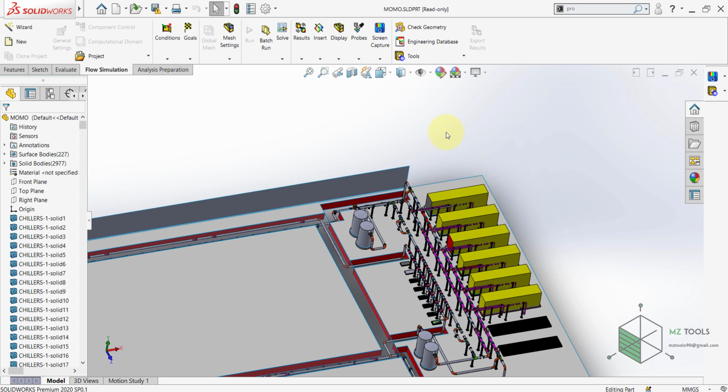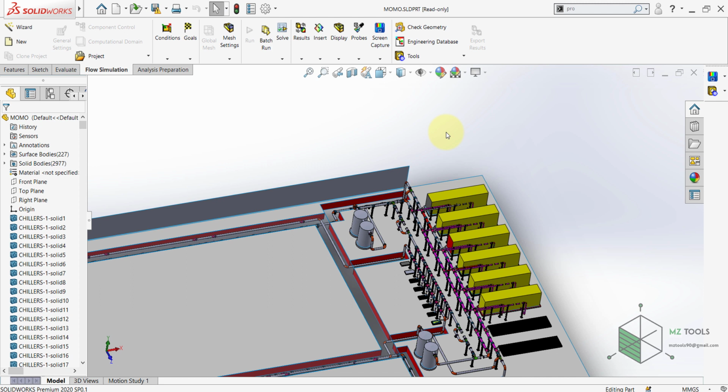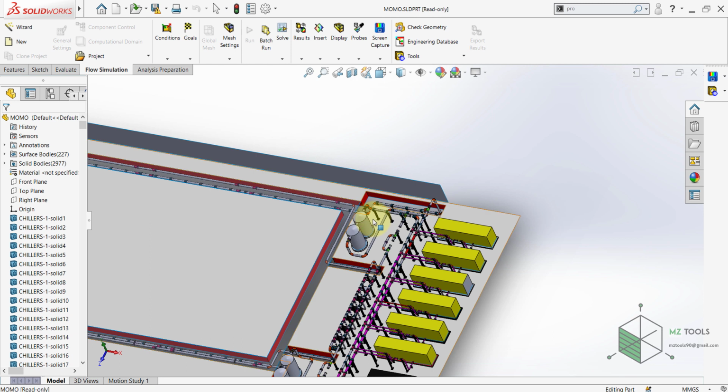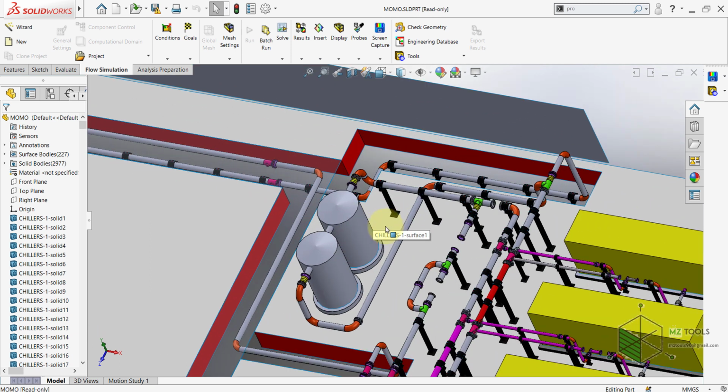The case is to design these tanks to supply the system with water, and the temperature of this water should be 16 degrees Celsius, while the entering water to the tanks will be 24 degrees. Here, you will have some water getting into the system, and the temperature will be 24, and by the end of a 5-minute period, you want the outlet of this tank to supply water with 16 degrees temperature.